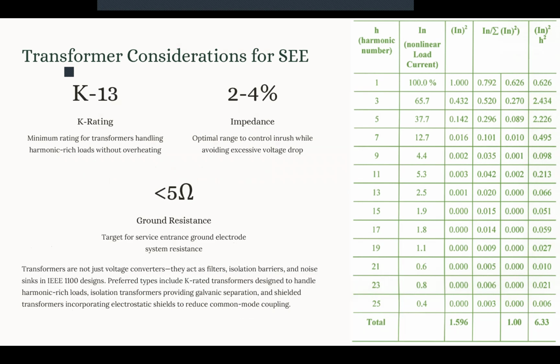Now, in a sensitive environment, the transformers are not just step-up or step-down devices. They also work as filters to attenuate the harmonic currents and common mode noise. They can be used as isolation barriers, providing galvanic separation between the utility sources and the sensitive loads. And they can be noise sinks, shielding the equipment from transient and high-frequency disturbances. These sensitive electronic devices are highly susceptible to harmonic distortion, voltage transients, and common mode noise. This gives the transformers a very critical role in mitigating those disturbances.